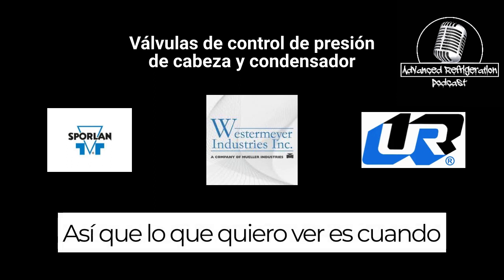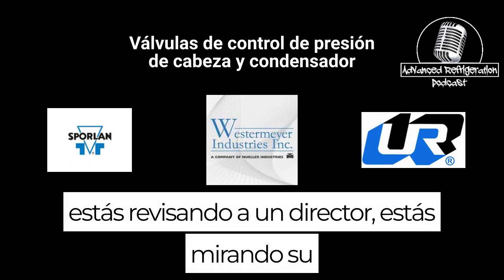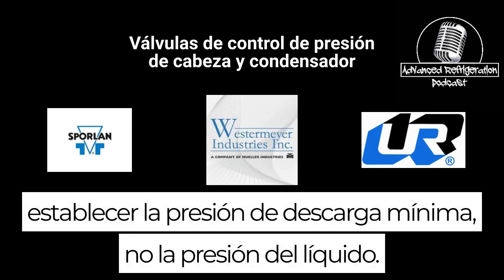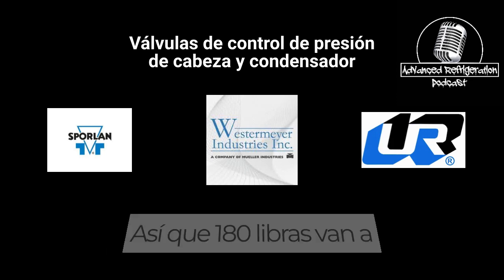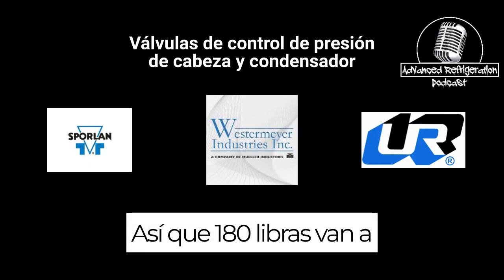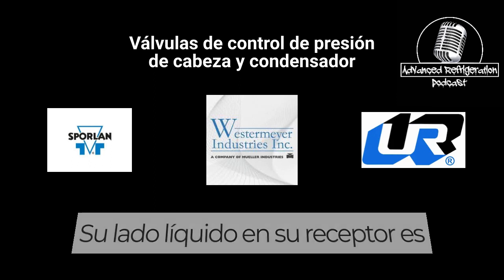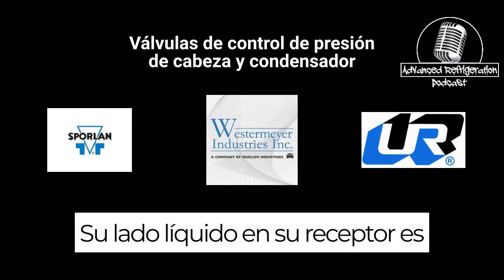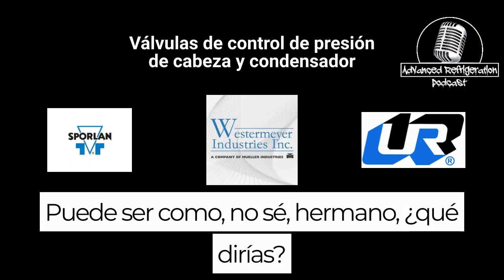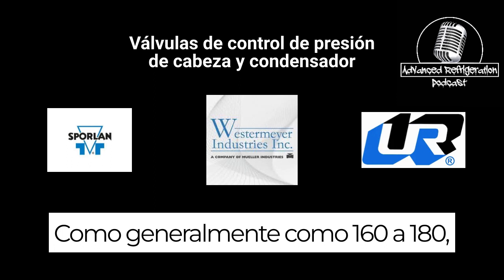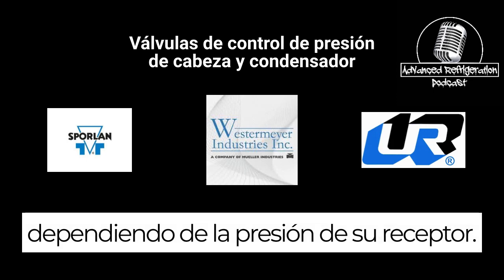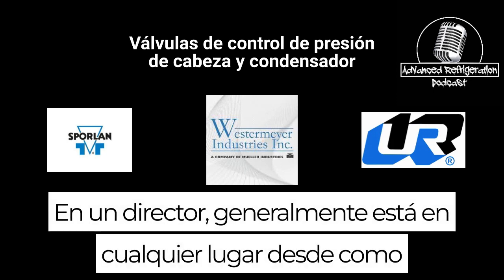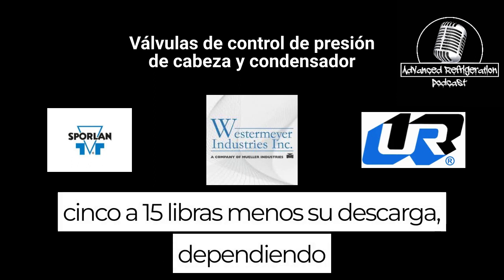So what I want to see, when you're checking a headmaster, is that you're looking at its setting, minimum discharge pressure, not liquid pressure. So that 180 pounds is going to be 180 pounds of your discharge. Your liquid side on your receiver is going to be a little less. It may be like, I don't know, bro, what would you say? Like generally 150 to 160 to like 180. I mean, your receiver pressure on a headmaster is generally anywhere from like 5 to 15 pounds less.